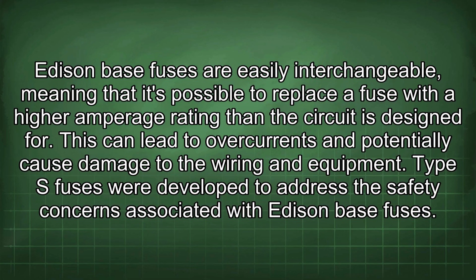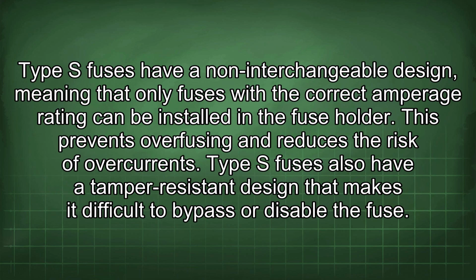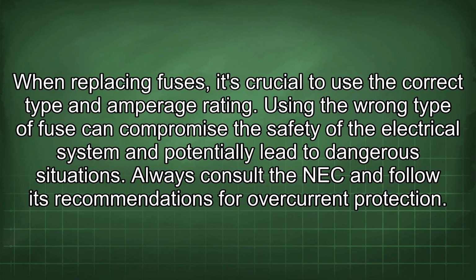Type S fuses were developed to address the safety concerns associated with Edison base fuses. Type S fuses have a non-interchangeable design, meaning that only fuses with the correct amperage rating can be installed in the fuse holder. This prevents overfusing and reduces the risk of overcurrents. Type S fuses also have a tamper-resistant design that makes it difficult to bypass or disable the fuse. When replacing fuses, it's crucial to use the correct type and amperage rating. Using the wrong type of fuse can compromise the safety of the electrical system and potentially lead to dangerous situations. Always consult the NEC and follow its recommendations for overcurrent protection.